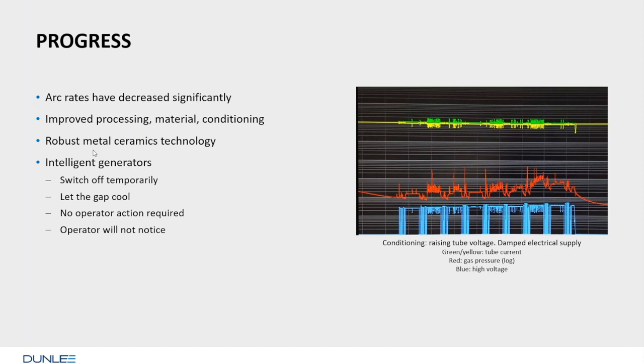Robust metal ceramics technology has been introduced. And last but not least, we offer intelligent generators. That's why a package of generator and tube is so important. An unintelligent generator just switches off, and if a tube spits a little bit, it breaks off the exposure. This is not good. Modern generators switch off temporarily for a short period, let the gap cool, and switch on again. The operator doesn't have to do anything, and will sometimes not even notice. So multiple discharges can occur in an exposure without noticing it. But that requires intelligent generators.